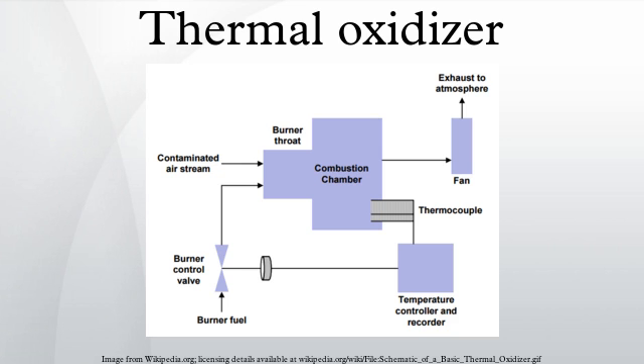Concentrations of methane in mine ventilation exhaust air of coal and trona mines are very dilute, typically below 1% and often below 0.5%. MTOX units have a system of valves and dampers that direct the air flow across one or more ceramic filled beds.